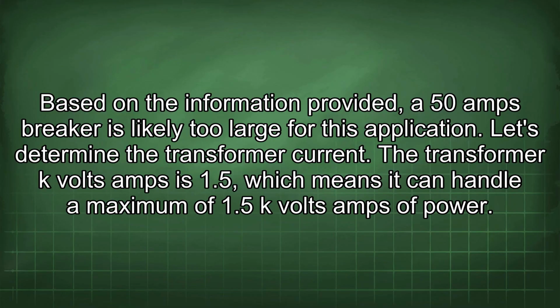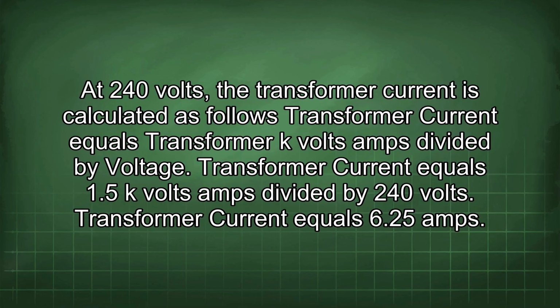Based on the information provided, a 50 amps breaker is likely too large for this application. Let's determine the transformer current. The transformer kVA is 1.5, which means it can handle a maximum of 1.5 kVA of power. At 240 volts, transformer current equals transformer kVA divided by voltage. Transformer current equals 1.5 kVA divided by 240 volts. Transformer current equals 6.25 amps.